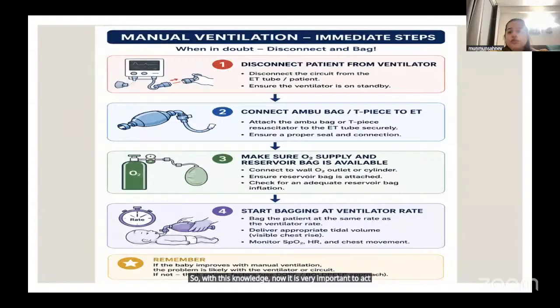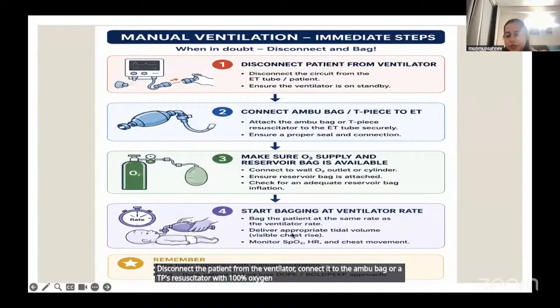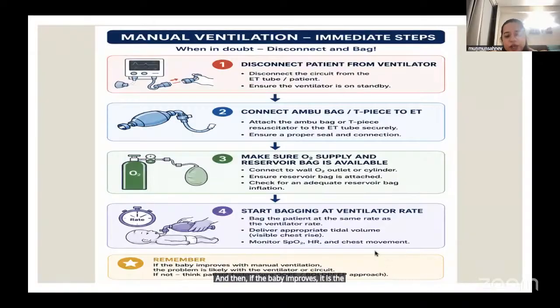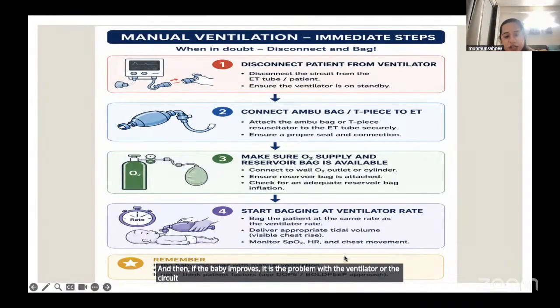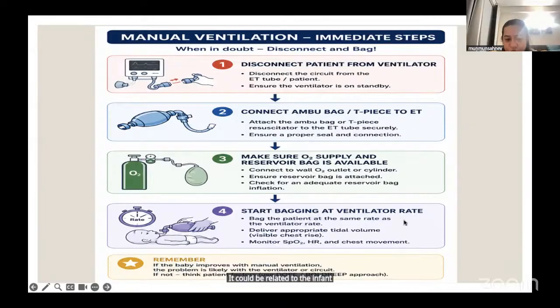So with this knowledge, now it is very important to act. The most common step whenever we have such a case and you are in doubt: disconnect the patient from the ventilator, connect to the AMBU bag or a T-piece resuscitator with 100% oxygen and start bagging. Then, if the baby improves, it is a problem with the ventilator or the circuit. And if it doesn't, it could be related to the infant or the ET tube. And now think of the DOPE approach.